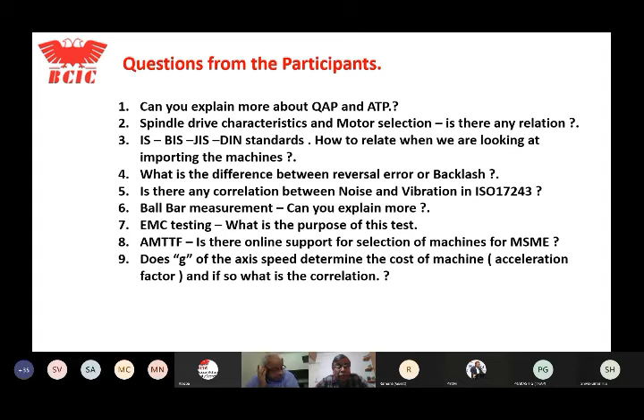Many times people don't know what kind of power they need at a lower speed. Obviously, when you want power at a lower speed, below the base speed of the motor, you need either a geared arrangement or a belt arrangement, so the motor runs above base speed while the spindle runs at a lower speed, and you still get the power you're looking for. So you have to make a choice.